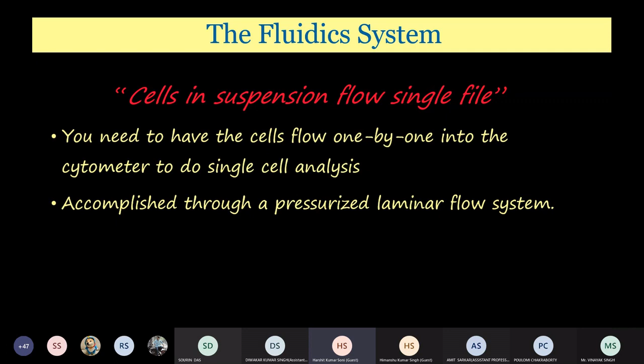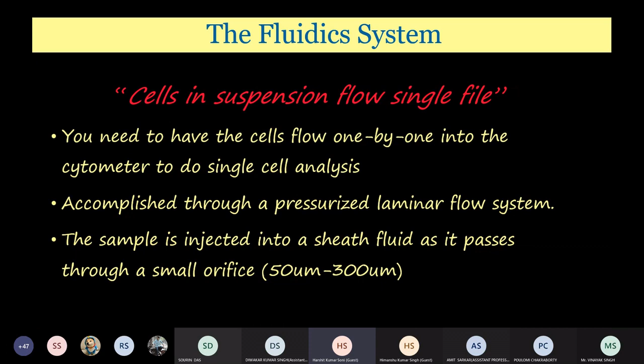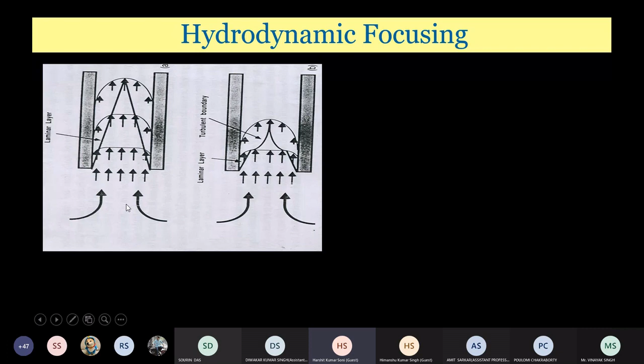The sample is injected into the sheath fluid as it passes through a small orifice of around 50 to 300 micron. This is how the laminar layer is built. As the sample goes through here, it starts focusing. If you see this way, you have the sheath fluid and the sample. The pressure difference between these fluids works in such a way that the cells form a narrow stream and only one cell can pass through here.